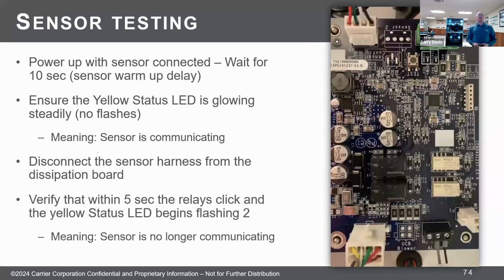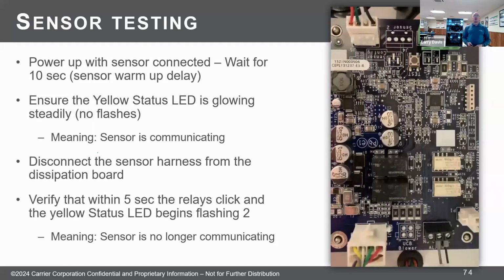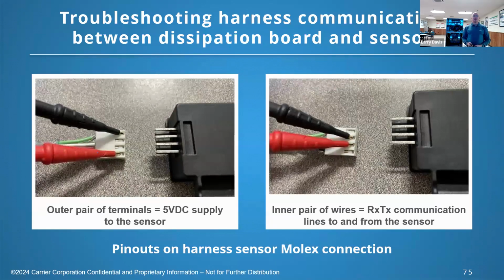Let's talk a little bit more about testing the sensor when we're troubleshooting these things. The test button will allow you to check the board to make sure the board's doing its thing. Now we want to test the sensor. One way is to pull it like we talked about before. Power it up, make sure you have a solid LED on the status light. Pull the harness for the sensor. If it starts flashing the fault code 2, then that's the sensor no longer communicating. So that tells us that the sensor was communicating before. So this is another video that we'll skip past.